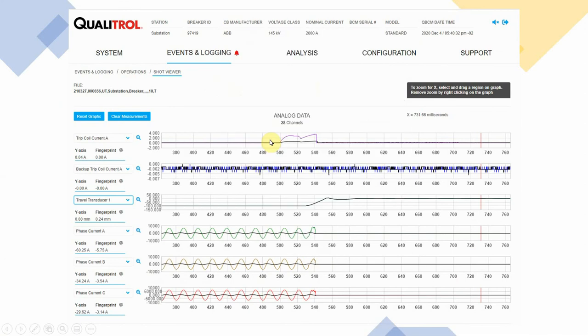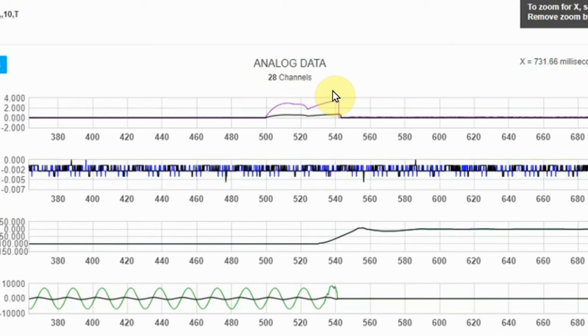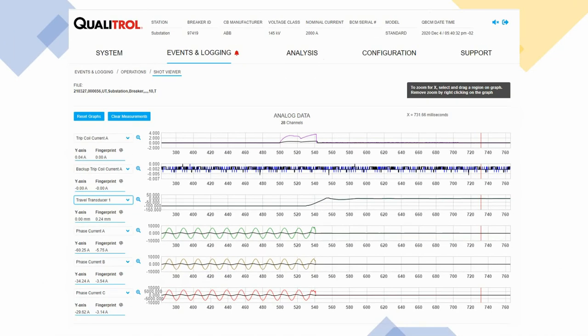Measuring the current passing through the coils during an event helps us see the complete signal pattern, or signature, of the coils for every single operation. These operations can be compared with a baseline operation and can be analyzed to detect any developing issues with the coil, for example, increasing or decreasing resistance, lubrication, etc. From the signature, not only the level of current can be analyzed, but also the timing as well as the complete area under the signature curve. So if there is any change in the behavior of the coils, it can be easily detected by monitoring the coil currents.